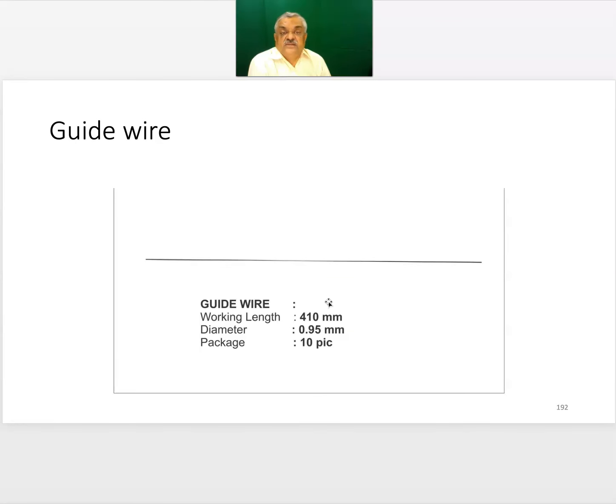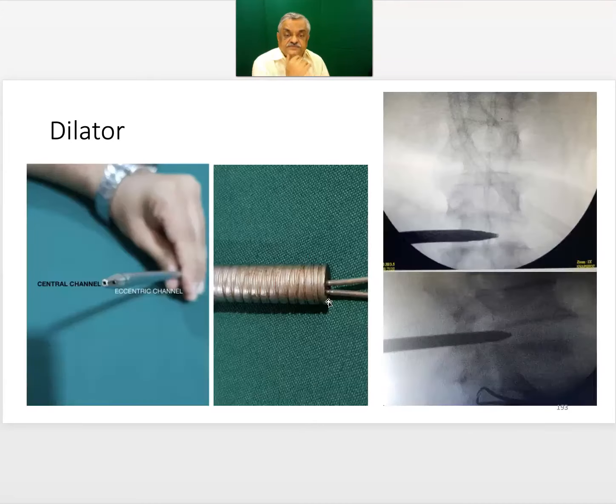Now a guide wire is used, which is 41 centimeters in length. It is 0.9 millimeters in diameter. It is available as a pack of 10. This guide wire goes through the needle and it has a length probably double the needle, so you can leave behind adequate length of the guide wire in spite of passing it to the tip of the needle. When you remove the needle over the guide wire, you are not lost.